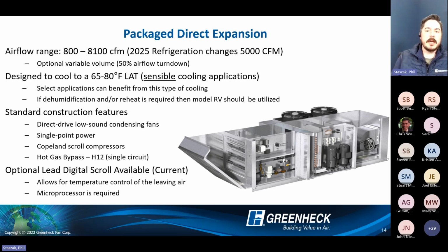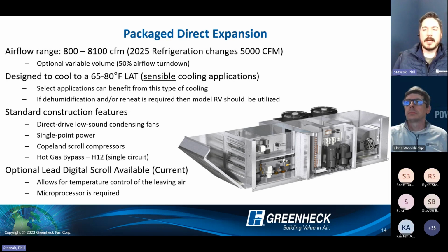So everything is currently R-410A, all the way up to 8100 CFM. But it looks like we're going to be changing that overall design to about a max of 5,000 CFM with this new A2L R454B type refrigerant. That really hits the majority of the market that we're looking at for the kitchens. 5,000 CFM seemed to be a pretty good happy point, and since we needed to redesign the whole box, that's kind of where we ended up landing.